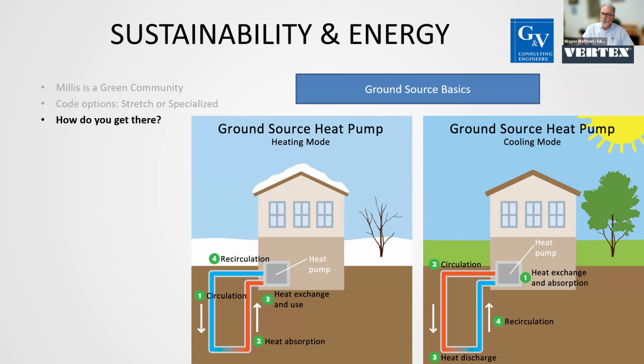It sounds great, but it's still electrically based. It's a fairly expensive system. It requires what we call wells. They're not wells in the sense of water wells for drinking and domestic use, but they're boreholes that are about 10 inches in diameter and range from 500 to 1,000 feet deep. And each one of those boreholes really only produces about 7 to 7.5 tons of heating or cooling. So you would need a lot of those, and there is a cost associated with that. And the Inflation Reduction Act is paying 30% of this type of system. And so you have to evaluate these carefully.